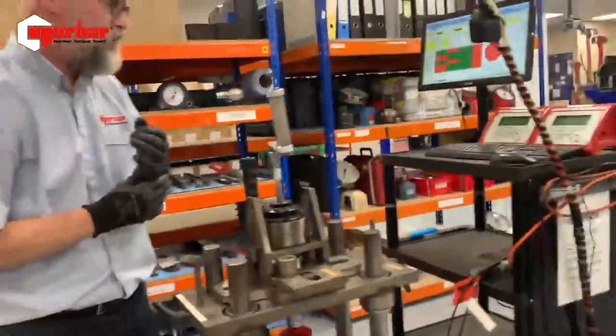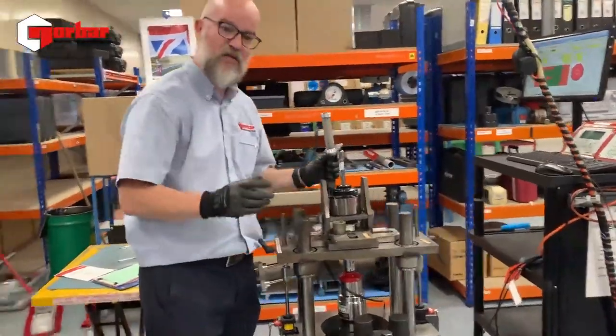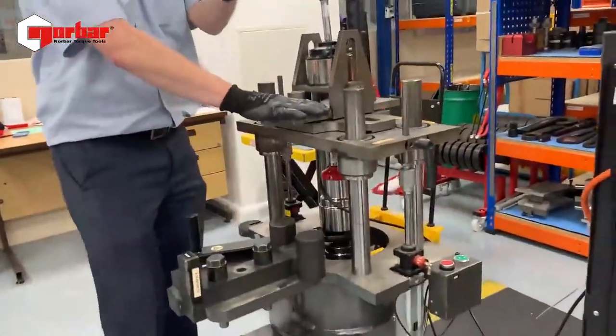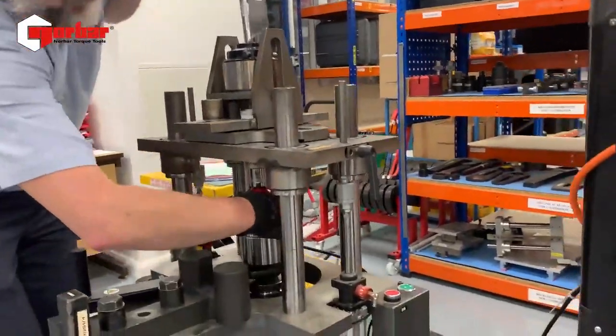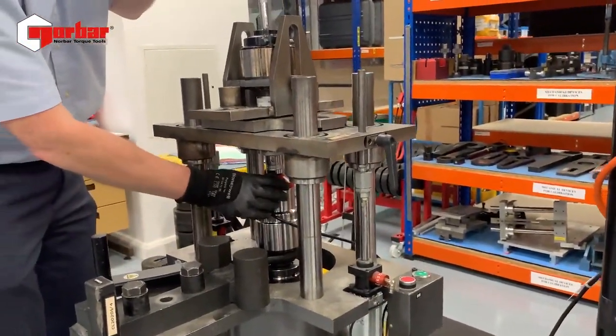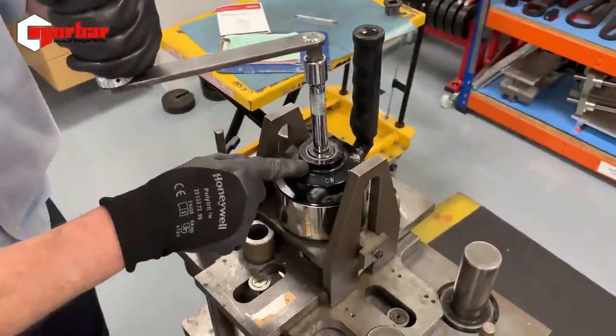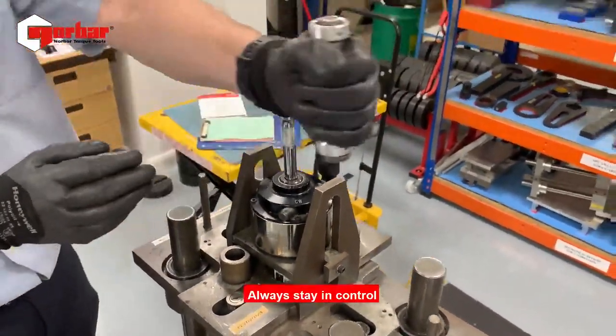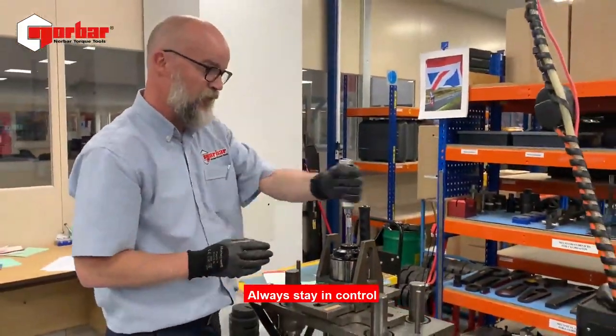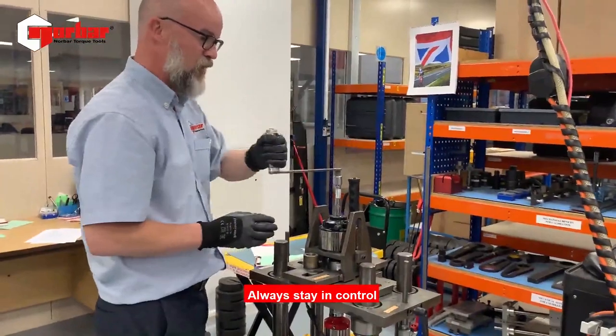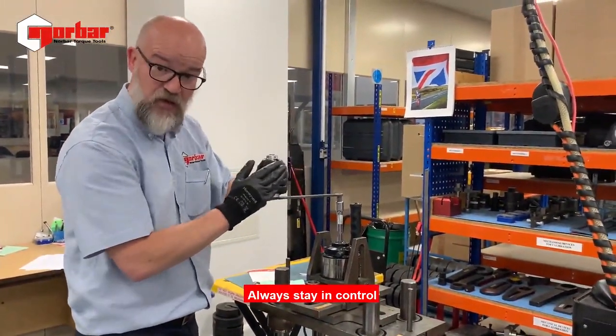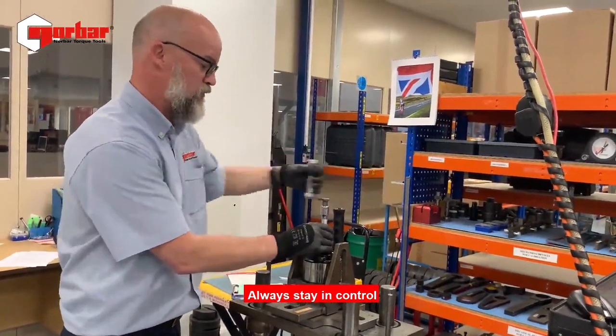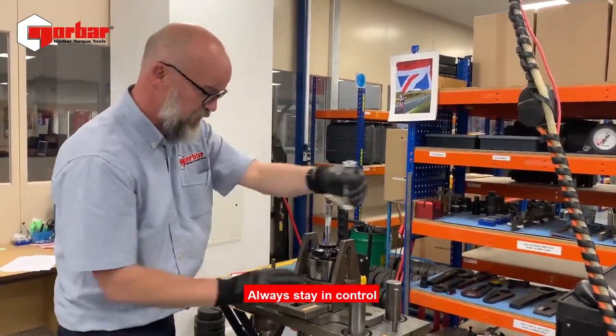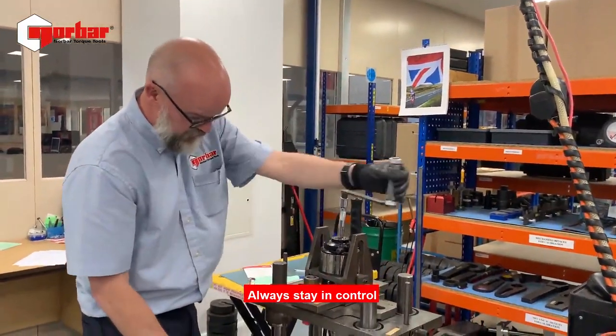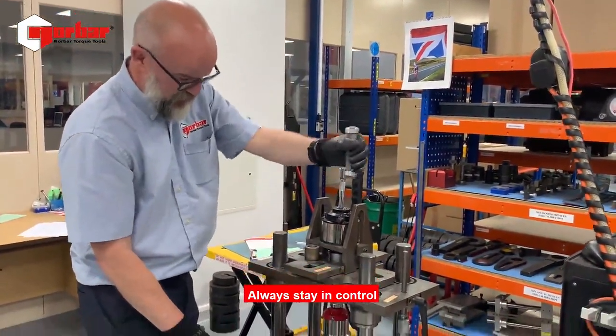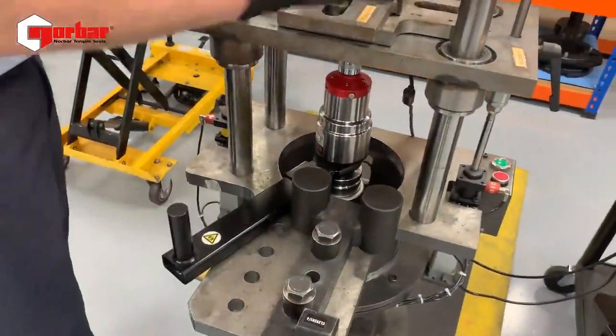Okay, so from here, what we're going to do is now relax. So again, we're going to apply a small amount of tension to the input. We're going to release the anti-wind-up if you've got one on the HT under test. We're then going to release the anti-wind-up on the input drive, and then with control we're going to back off. Okay, we are not going to let go, we're going to be in control. And again, the head's going to come loose, and then we're just going to be checking the output. So again, here, zero torque, zero torque.